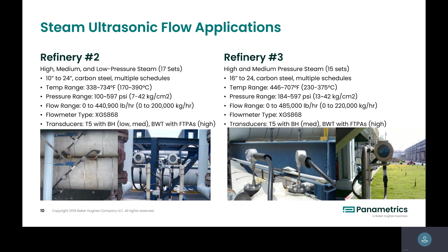Again, this one is using our different type of transducers, our T5 transducers with barrel holders. I'll show you some of those pictures, what they look like, a little bit later in the presentation, but it has a capability of doing low, medium, and high pressure overall. And it's just another example. That's our transmitter right there, but you can see the transducer design. Mostly we always see ultrasonic being the tilted diameter, or shooting across the pipe. Sometimes we'll install just on the top, either for access or ease of installation. So we have that flexibility of how we install the transducers. But again, with 16 to 24 inch lines, big steam lines, the rangeability is really a good advantage ultrasonic brings to the market.